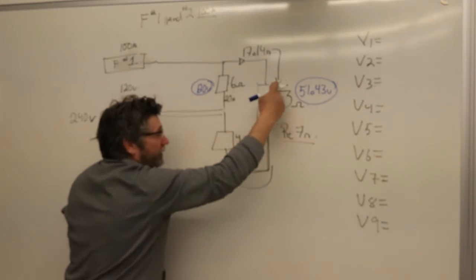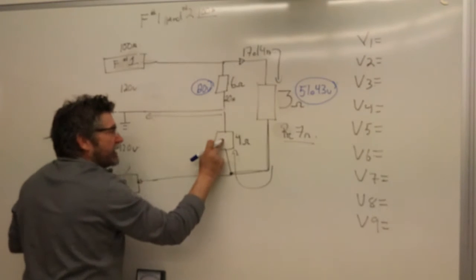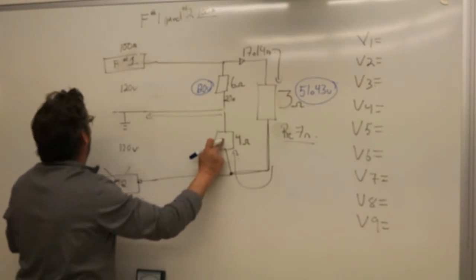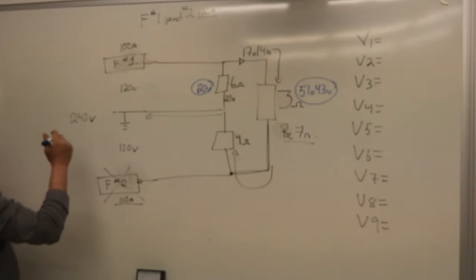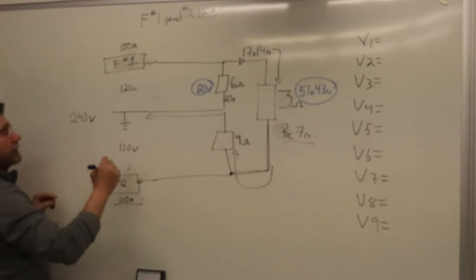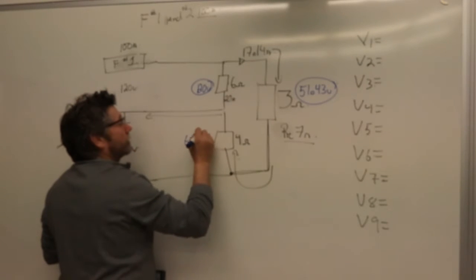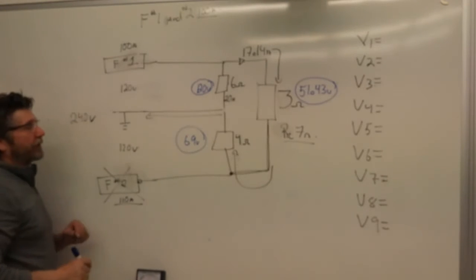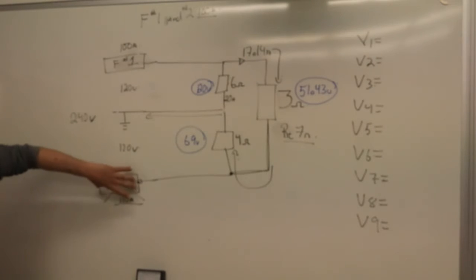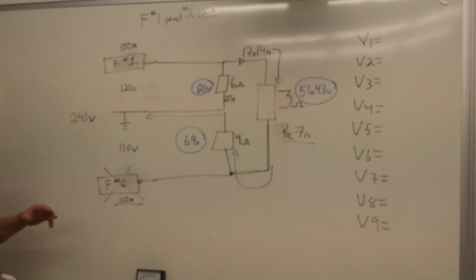And then that 17 amps comes in here. 17 amps over 4 ohms is going to cause a 69 volt drop, ish. We left it alone. I like all that. The voltage over here we can do later.